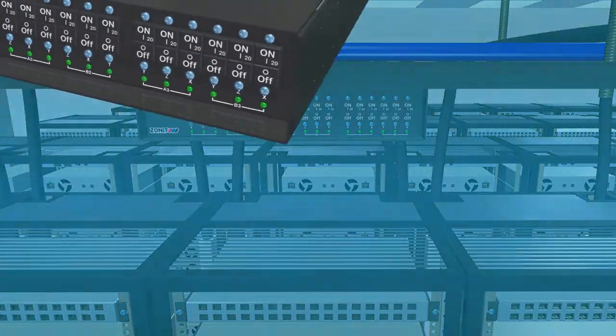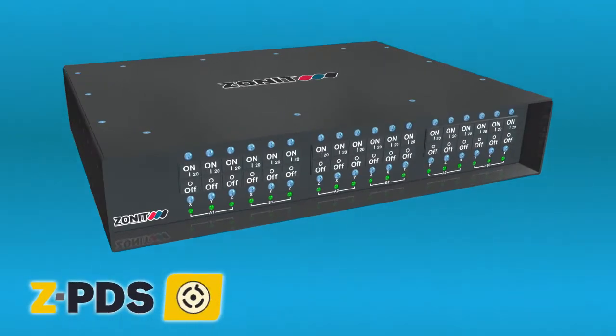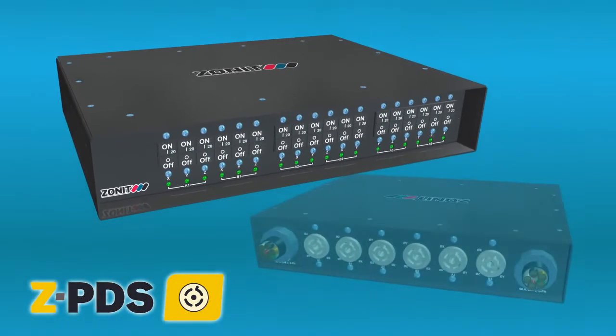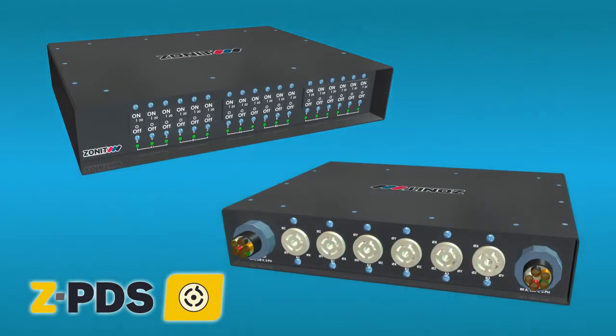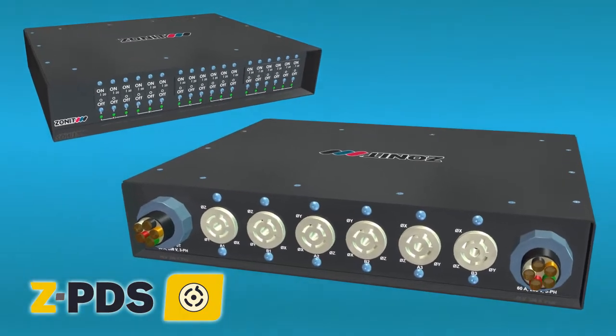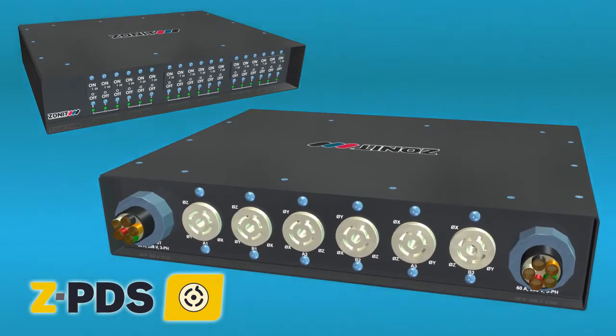Why did Zonit create the Z-PDS? The Z-PDS system was designed to address the technical limitations and eliminate the pain points of existing methods of power distribution to the rack. It can be combined with traditional methods to accomplish these goals. With Z-PDS, you can easily and flexibly deliver the amperage, voltage, and receptacle type you need at the rack to feed your plug strips or your IT equipment directly.